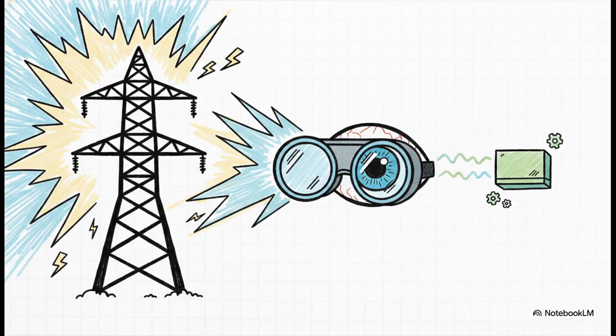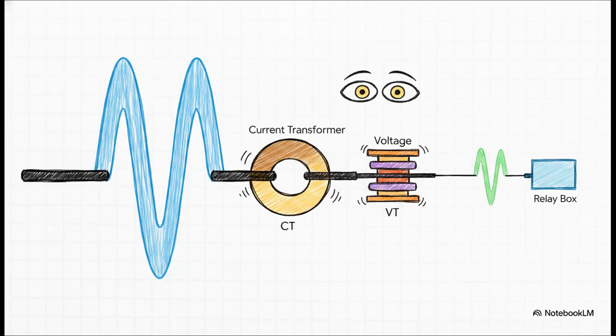But here's the catch. To make that delicate dependability versus security decision, the relay needs perfect data. So how do relays actually see the grid to make these choices? I mean, they don't interact with the massive 500 kilovolt high voltage lines directly. If they did, they'd instantly vaporize. They have to rely on translators. We call these translators instrument transformers, and they act as the eyes of the entire protection system.